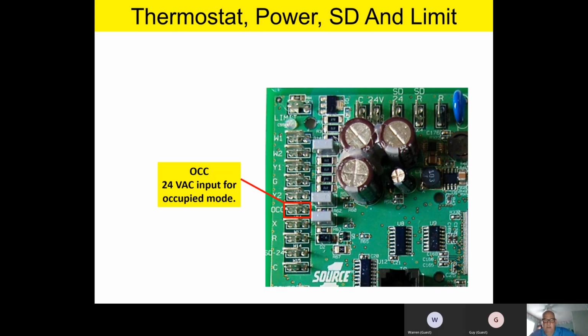And then it's just going to be strictly driven by thermostat input. Now, if you don't put that jumper there, is it going to work? Absolutely. But we have found that on a conventional 24 volt thermostat hookup, the board likes to be occupied. And so now basically at that point, unless you have an occupied, unoccupied function on the thermostat, then go ahead and just jumper that, and that'll give you what seems to be a little more reliable operation.